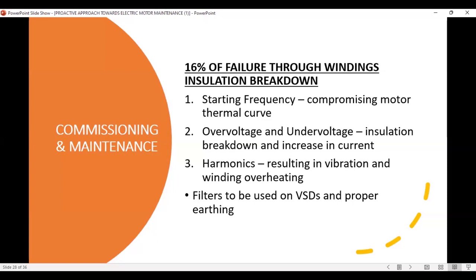Over voltage and under voltage cause a rise in current and insulation breakdown. So you put in correct settings, 10% and 10% for over voltage and under voltage, so that when there's a rise or a dip in voltage, the motor is protected. The circuit is cut off to protect it from failure. Harmonics have been found to cause heating and vibration of motors. So especially for a VSD with a far distance between the motor and the VSD, we must ensure that inductors are installed to protect the motor from harmonics, which will cause heating and vibration. Vibration can cause failure, and we must ensure proper earthing of our application so that all these issues can be resolved. Next slide.